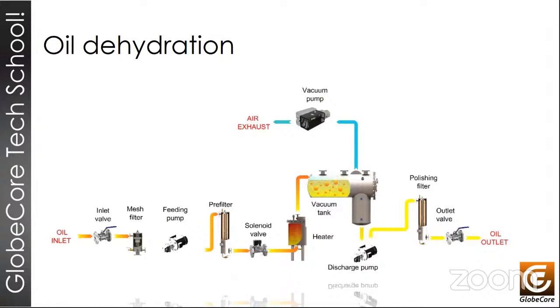So in the heater, the temperature of the oil is increased to, say, 65 degrees, no more than that, because we don't want oil decomposition. And then that oil goes into the vacuum chamber, where pressure is reduced to levels where you can safely heat the oil. So all gaseous pollutants, combustible gases, and water can be extracted from the oil using vacuum at this time. And the vacuum pump discharges all of this extracted material into the environment.